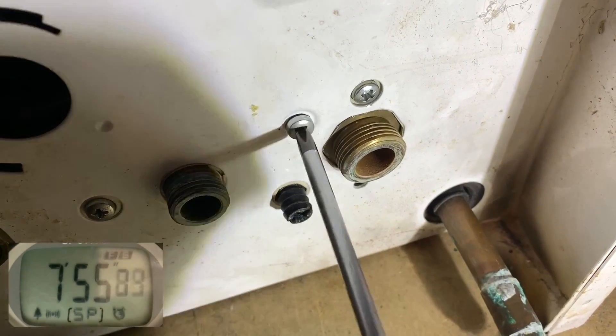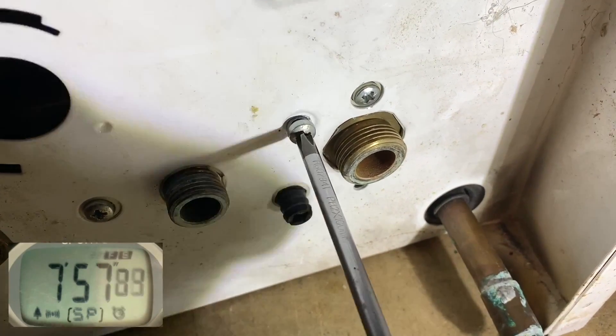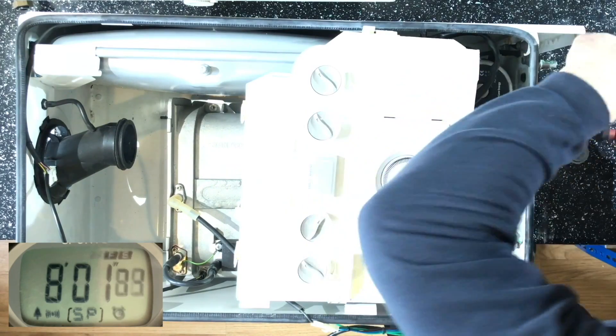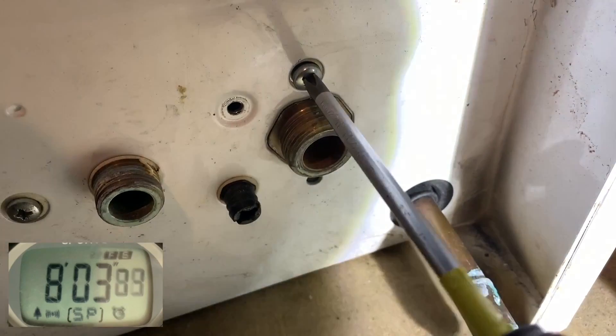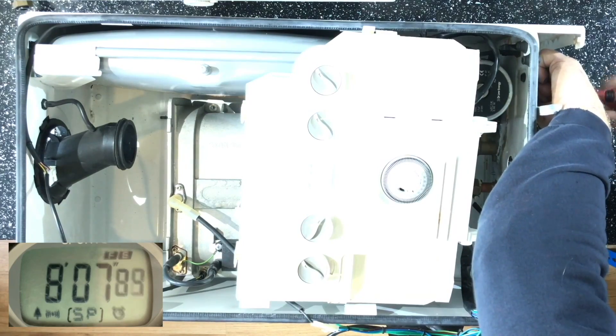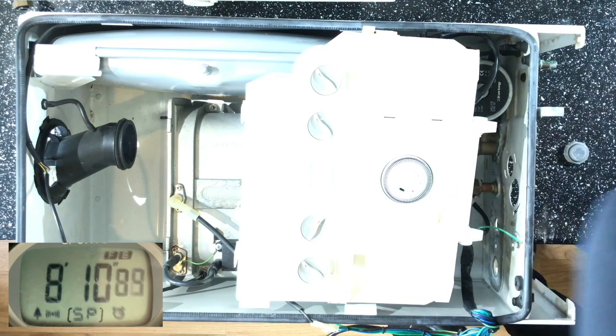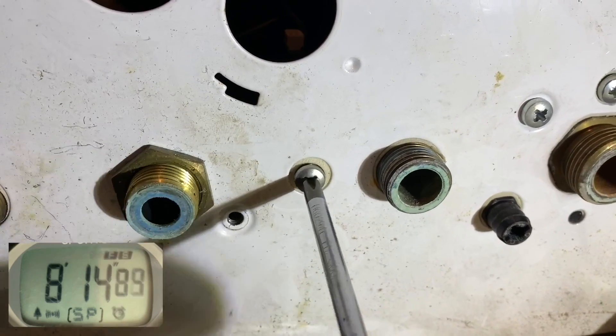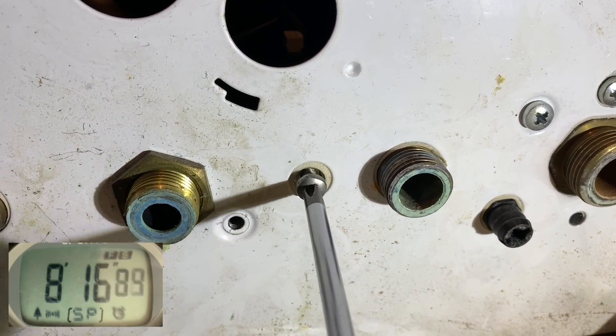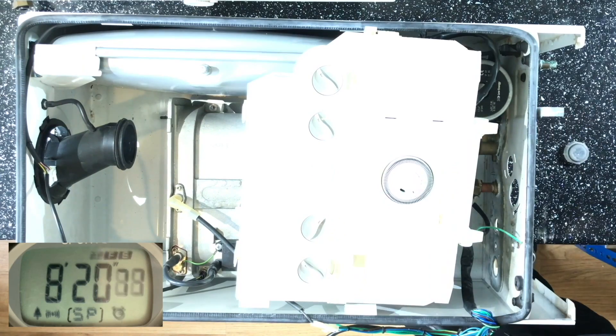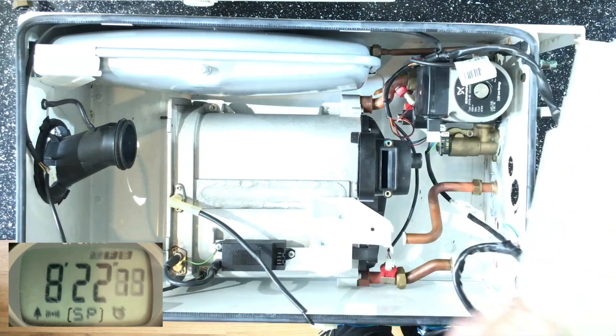So what I'm doing now is I'm just undoing these securing screws to the right-hand side hydro block where the pump is, the flow turbine, and the low-water pressure sensor. I'm going to take this all out as one complete unit, which again is just a matter of undoing three screws and undoing the return pipe which goes to the bottom of the heat exchanger.